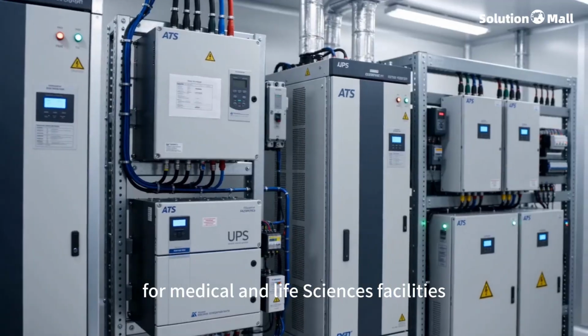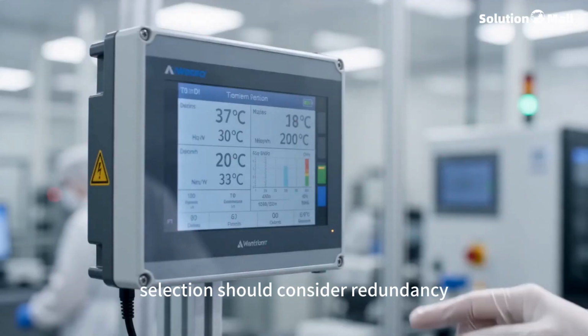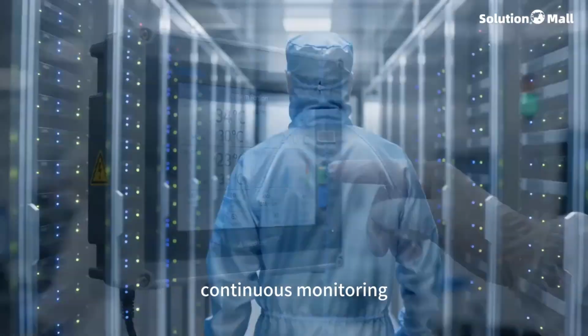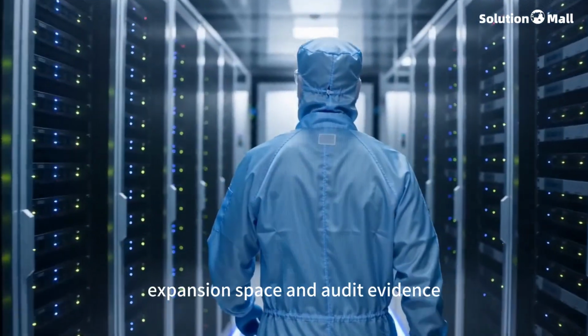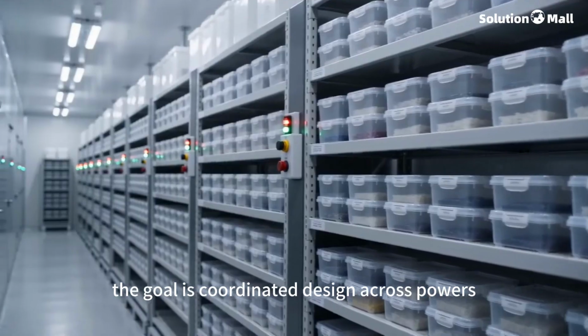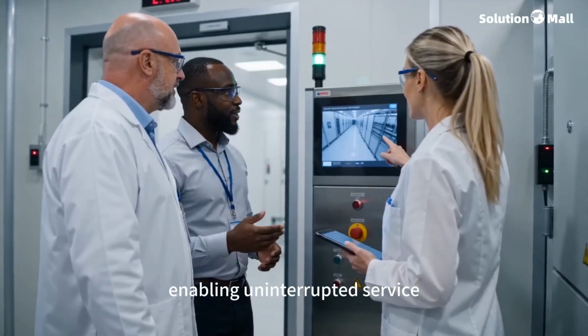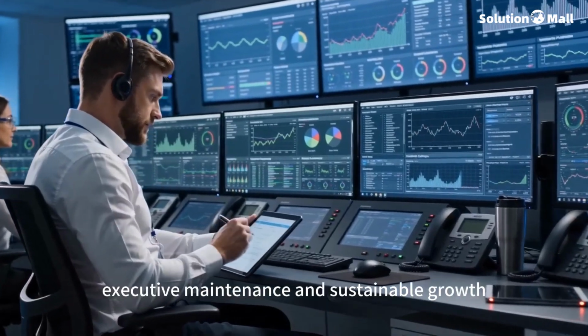Selection should begin with system logic, not isolated product specifications. For medical and life sciences facilities, selection should consider redundancy, maintainable distribution, continuous monitoring, network isolation, backup and enclosure, expansion space, and audit evidence. The goal is coordinated design across power, cooling, monitoring, network, and security systems, enabling uninterrupted service, predictable risk, traceable events, efficient maintenance, and sustainable growth.